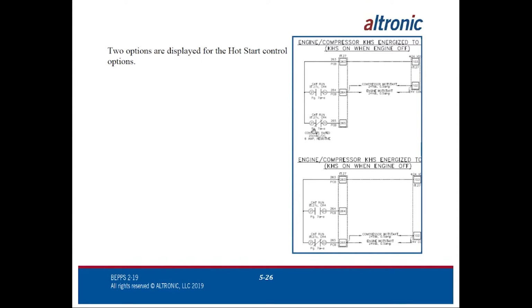Now, one reason why I like to use this relay and point this out is it's the cat run relay, CR4, both relays. Terminal 22 and terminal 24 go to different places. Terminal 21, shown twice, goes to one place. There are not two terminal 21s on that relay. Terminal 21 is drawn twice to indicate two different states of that relay. There are still only three terminals on that relay: 24, 22, and 21. We just draw it twice because we draw it in two different states. So please make note of that. Any questions on that part?